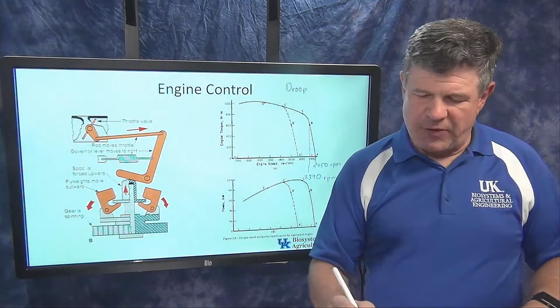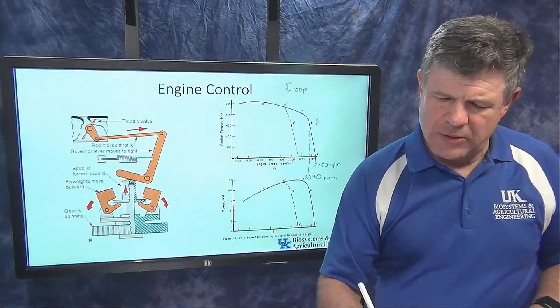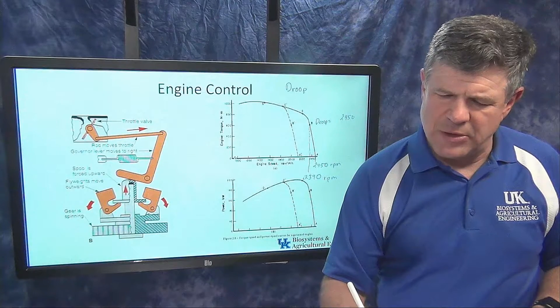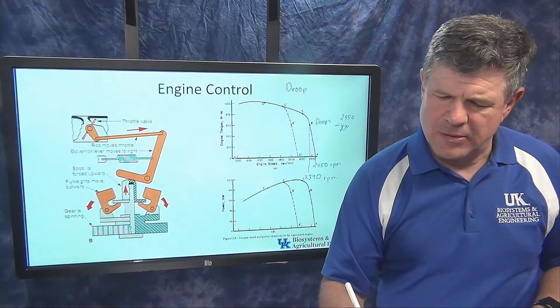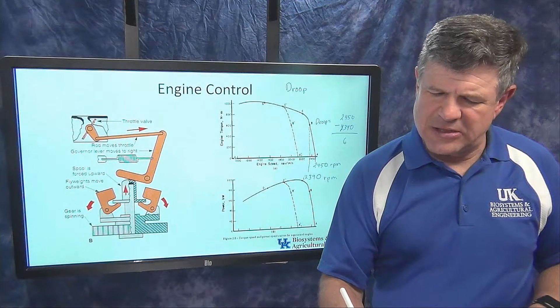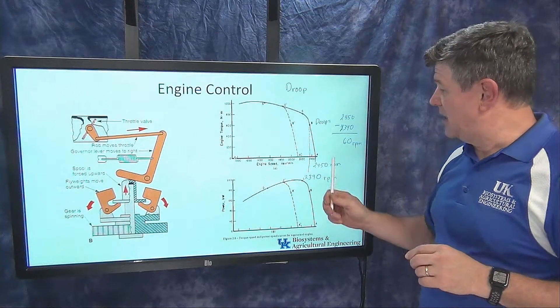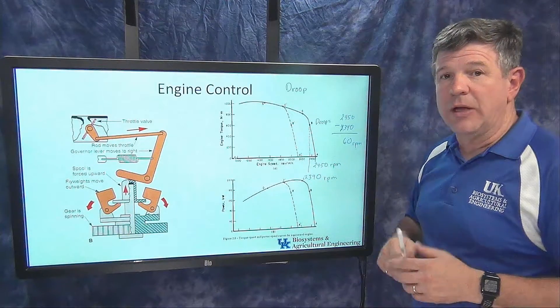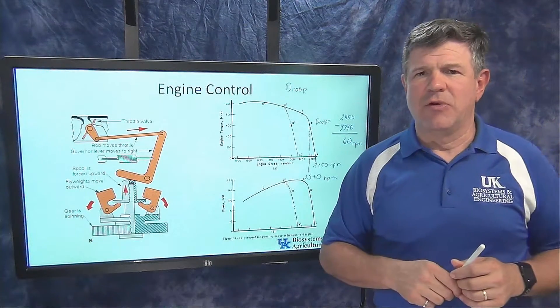So what is the droop? If I calculate the droop for this engine, it equals 2,450 RPM minus 2,390 RPM. Subtracting those numbers gives me 60 RPM as my governor droop. What that's saying is, from the maximum speed at wide open throttle to where the governor is at its limit — that's all it can control, it's out of range — that speed change is going to be 60 RPM. That's the governor droop.